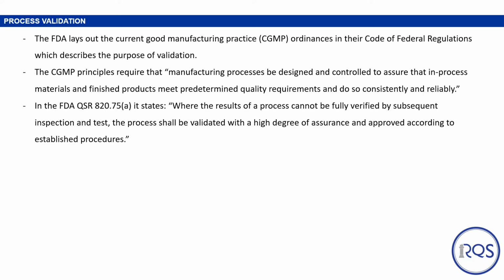The FDA lays out current good manufacturing practices, or CGMP, ordinances in their Code of Regulations, which describe the purpose of validation. The CGMP principles require that manufacturing processes be designed and controlled to assure that in-process materials and finished products meet any predetermined quality requirements and do so in a consistent and reliable way. The FDA QSR Part 820.75(a) states that where the results of a process cannot be fully verified by subsequent inspection and test, the process shall be validated with a high degree of assurance and approved according to established procedures.